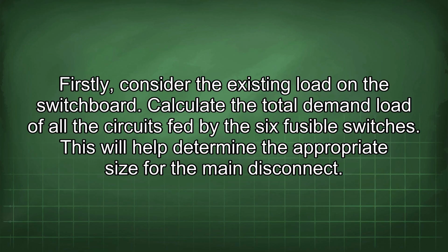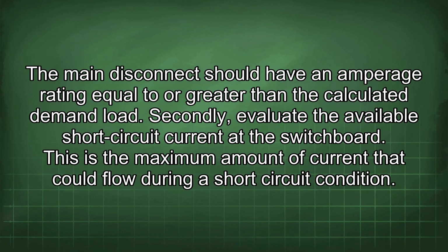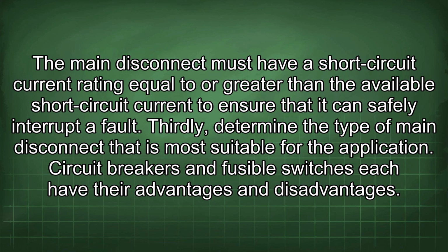Firstly, consider the existing load on the switchboard. Calculate the total demand load of all the circuits fed by the 6 fusible switches. This will help determine the appropriate size for the main disconnect. The main disconnect should have an amperage rating equal to or greater than the calculated demand load. Secondly, evaluate the available short circuit current at the switchboard. This is the maximum amount of current that could flow during a short circuit condition. The main disconnect must have a short circuit current rating equal to or greater than the available short circuit current to ensure that it can safely interrupt a fault.